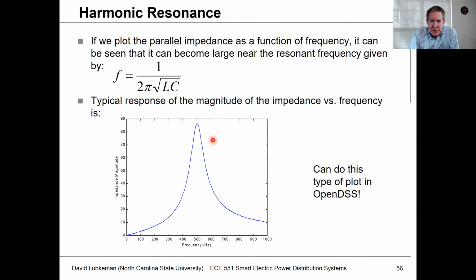So for example, if I were going to plot this parallel RLC impedance, I might get a characteristic that looks something like this right here. Need to move something on my zoom settings. So you can see that it's peaking out around 500 hertz or so. And so anytime I have a harmonic being injected at this point in the curve where it spikes, then this means I can get what's called a resonant overvoltage. The amount of this peak is going to be reduced by the amount of resistance in the circuit. But the resonant frequency is going to be about 1/(2π√(LC)) in terms of hertz.